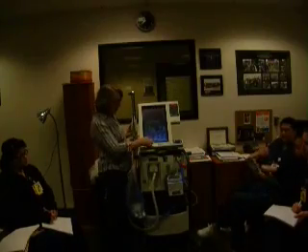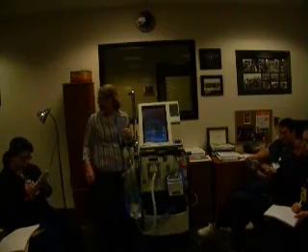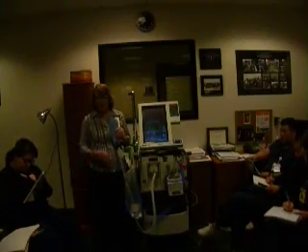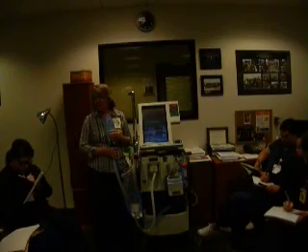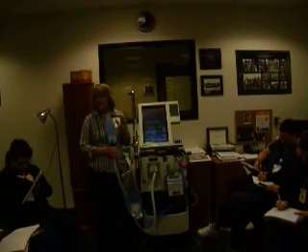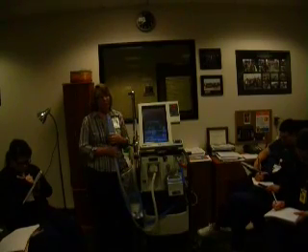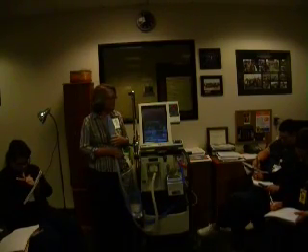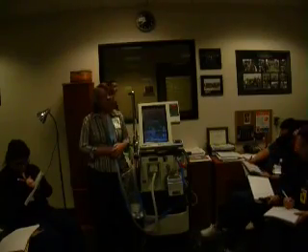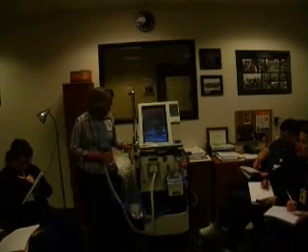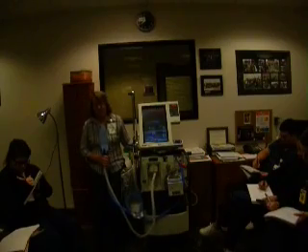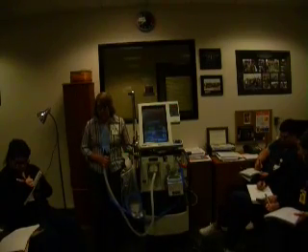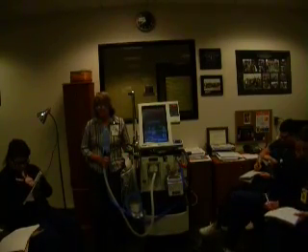Okay? All right, so let's see. Oh, there is apnea setup. That's your apnea backup. If your patient goes apneic, the machine will kick in and breathe. Default time is 20 seconds. Other than that, unless your patient's on a really low rate, it'll be set the same as your settings. But always 100%. Apnea backup will always be at 100% no matter what the FiO2 is, because if our patient went apneic, we want to provide the support for them.